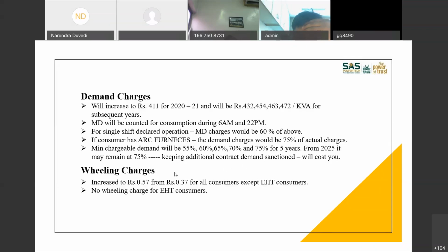Billing charges, as I explained, they will vary from place to place. The basic rate they have increased from 0.37 to 0.57, and all EHT consumers, those who consume power at a voltage beyond 66 kV, will not be charged any wheeling charges, because in most of the times they are just next to MSEDCL substations, right? I mean, 220 kV or 440 kV substation will be there, and next to that this industry will be there. So first thing is voltage is more, so current is comparatively very less for the same power. And second thing is the distances are also comparatively very less. So distribution losses are less. That's why they won't be charged wheeling charges.